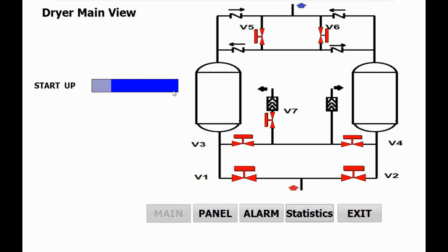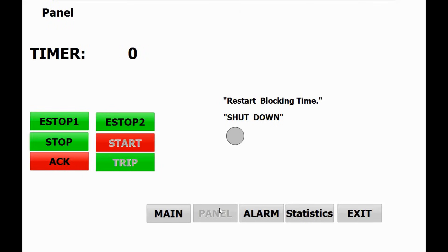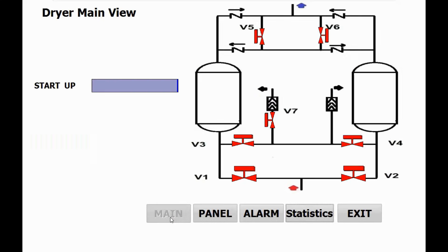You can see that during the CPU transition from stop to run mode, we have a startup timer. This startup timer avoids starting the machine immediately — we need to prepare everything first. The timer ensures all electrical components inside the control cabinet are live, after which we have the possibility to put the dryer machine in run mode. We need to wait until the restart blocking time has passed.